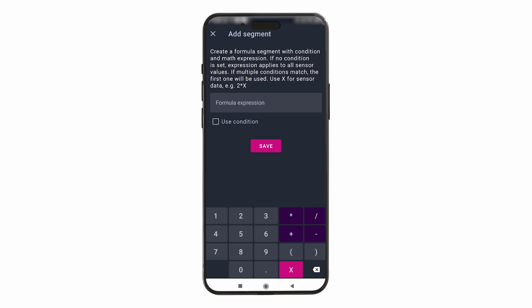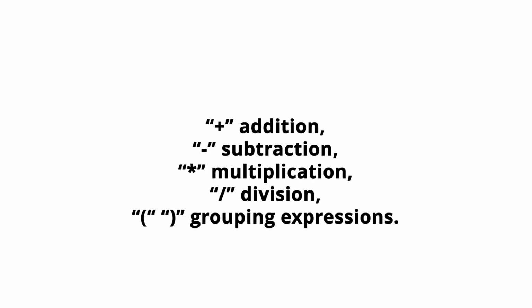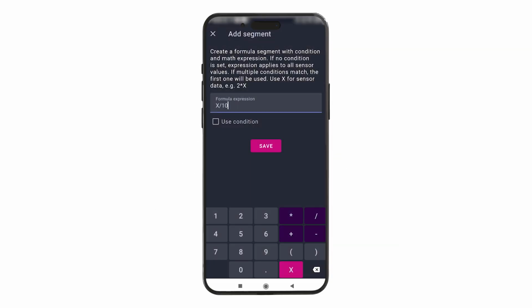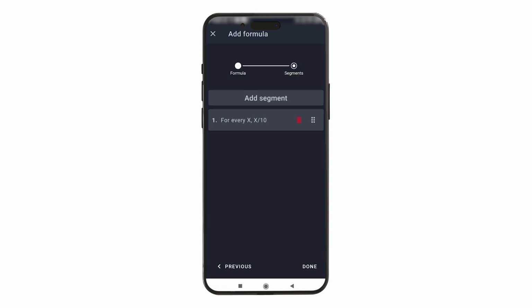The conversion formula must be mathematically correct and limited to 32 characters. To reference the value measured by the sensor, use the special character X. For example, doubling the value sent by the sensor can be achieved with the formula X times 2. In the formula segment, you can use basic special characters such as addition, subtraction, multiplication, division, and grouping expressions. In our case, every 10 pulses generated by the electricity meter corresponds to 1 watt-hour of consumed electricity. Therefore, the applied formula is the count of pulses X divided by 10.